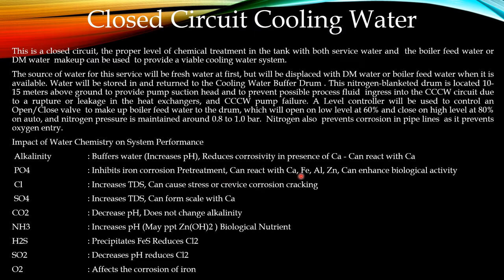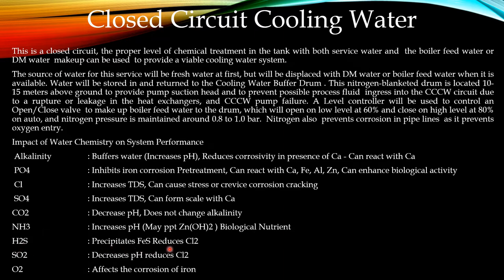Phosphate inhibits corrosion in pre-treatment; it can react with calcium, ferrous, aluminum, and zinc. However, phosphate is a nutrient so it can enhance biological activity and increase microorganism growth. If chlorides are present, that will increase the TDS, cause stress, and cause crevice corrosion and cracking in the pipeline. If sulfate is present, that will increase TDS and can form hard scale with calcium inside the pipeline. Carbon dioxide will decrease the pH but does not change alkalinity. Ammonia, if present, increases pH, may precipitate zinc hydroxide, and is also a nutrient for biological or microbiological growth.